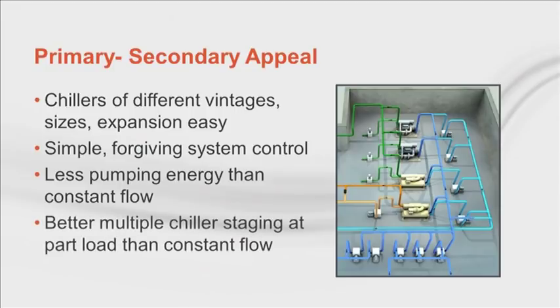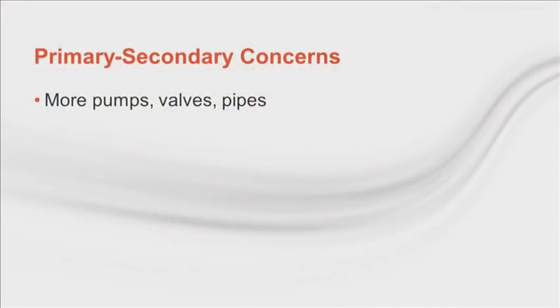At part load, chillers are staged when the loads get high enough to require another chiller's flow. Circuit isolation is easy to accomplish. The chillers are happy and the coils are happy at a lot more loads. But this happiness comes at a price: more pumps, valves, electrical and pipes to connect them.